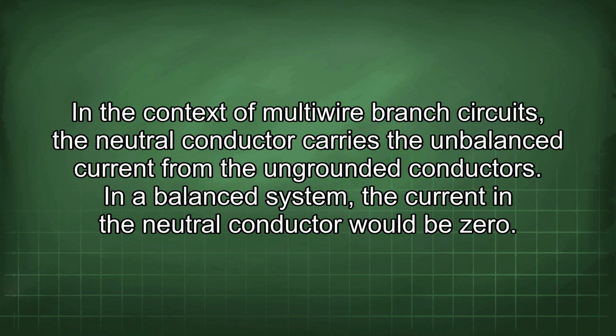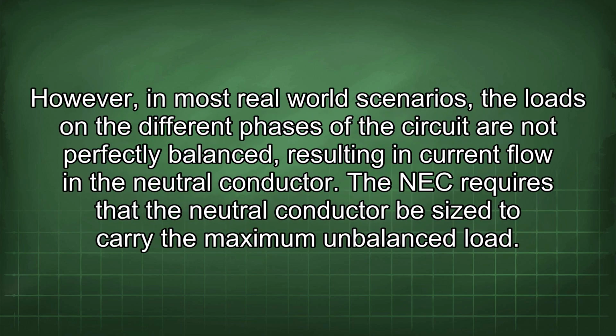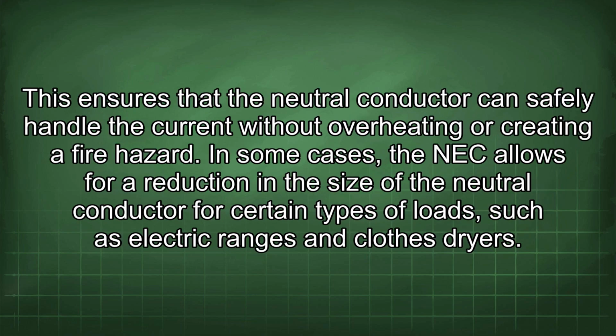In a balanced system, the current in the neutral conductor would be zero. However, in most real-world scenarios, the loads on the different phases of the circuit are not perfectly balanced, resulting in current flow in the neutral conductor. The NEC requires that the neutral conductor be sized to carry the maximum unbalanced load. This ensures that the neutral conductor can safely handle the current without overheating or creating a fire hazard.